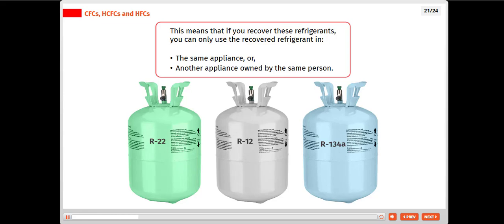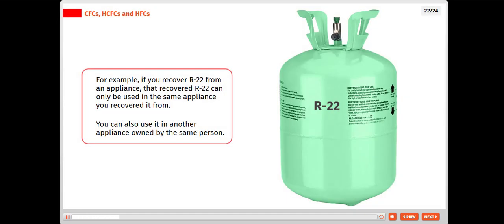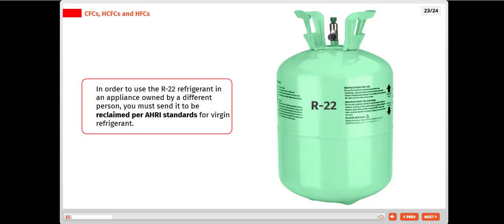This means that if you recover these refrigerants, you can only use the recovered refrigerant in the same appliance or another appliance owned by the same person. For example, if you recover R22 from an appliance, that recovered R22 can only be used in the same appliance you recovered it from. You can also use it in another appliance owned by the same person. In order to use the R22 refrigerant in an appliance owned by a different person, you must send it to be reclaimed per AHRI standards for virgin refrigerant.